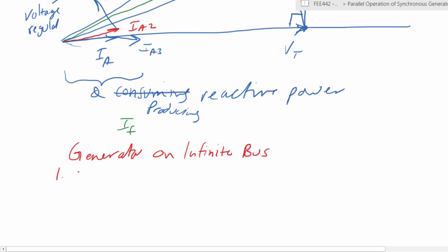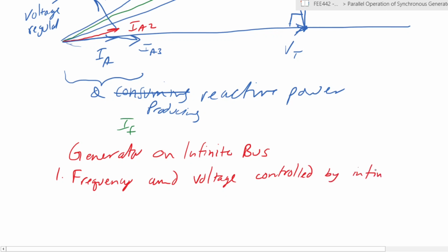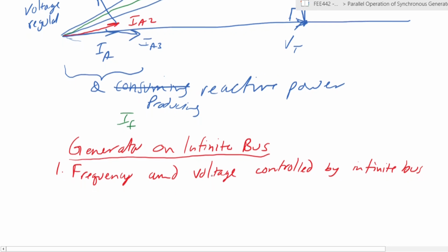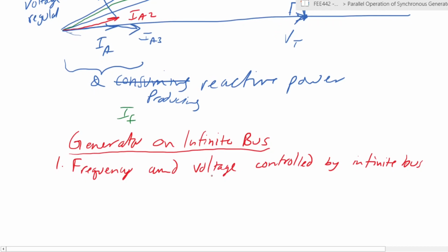Number one, frequency and voltage are controlled by the infinite bus. When your generator is connected to an infinite bus, you cannot change the value of frequency and voltage at which you supply. You must match those values because they are dictated by your infinite bus.